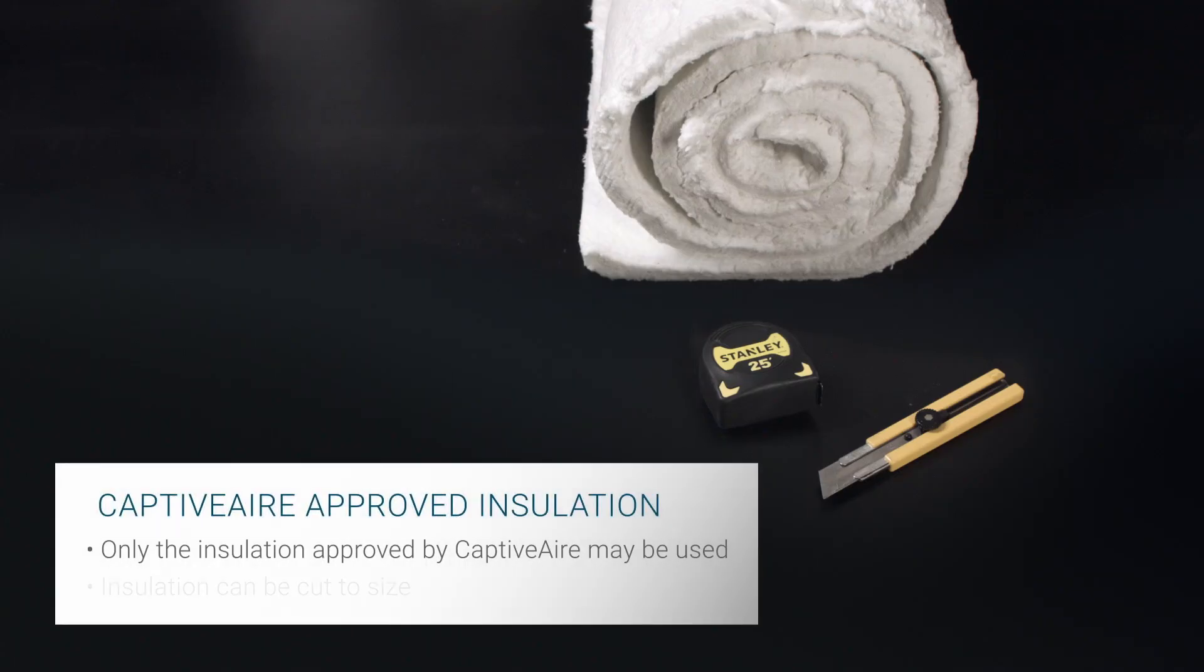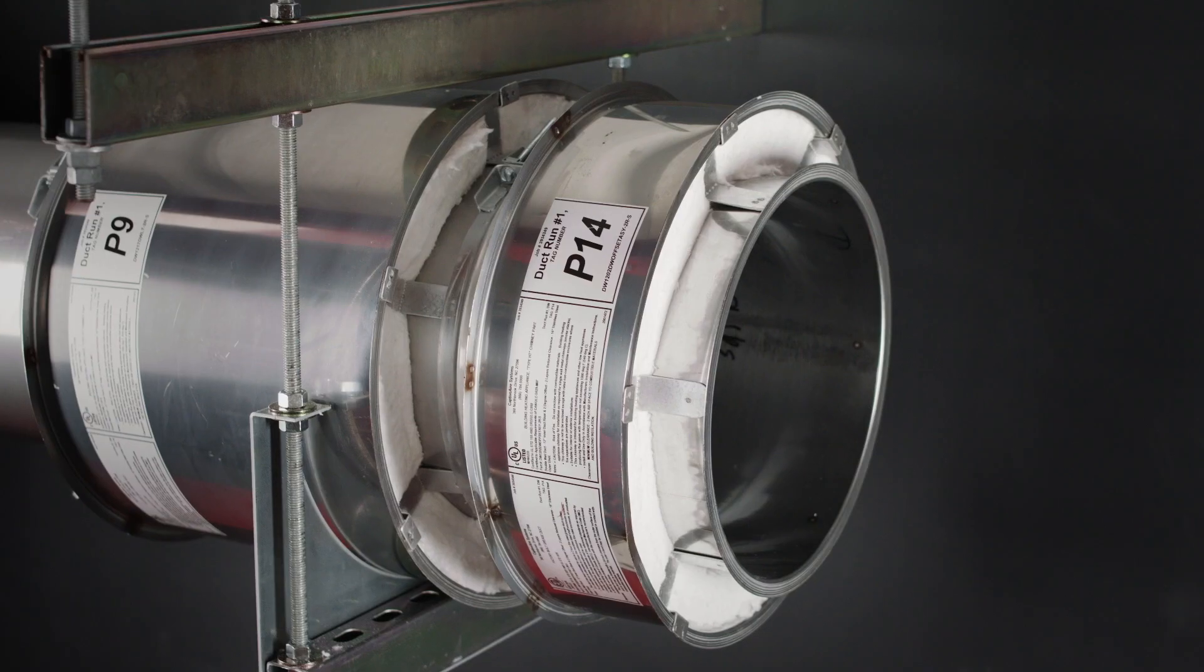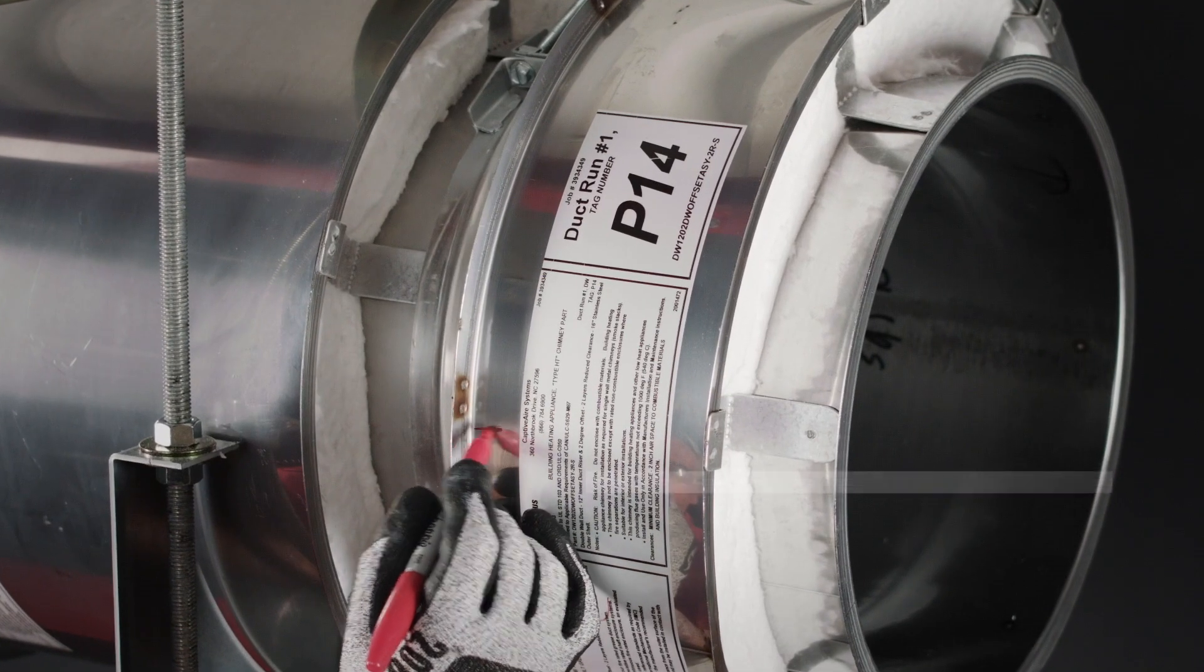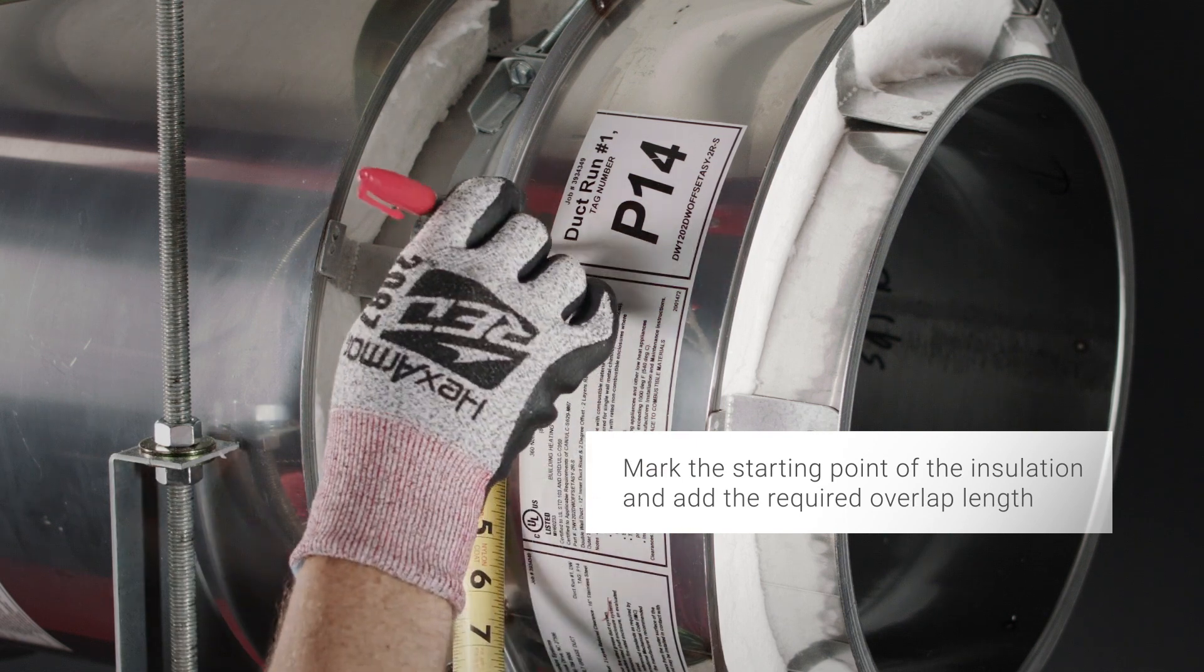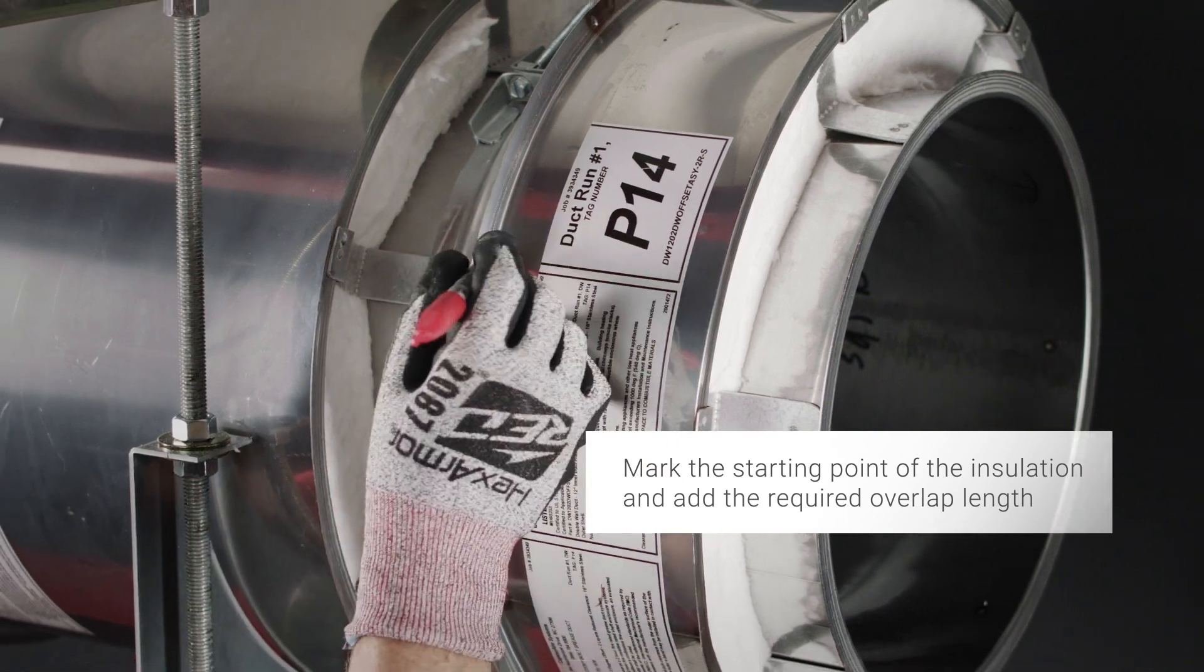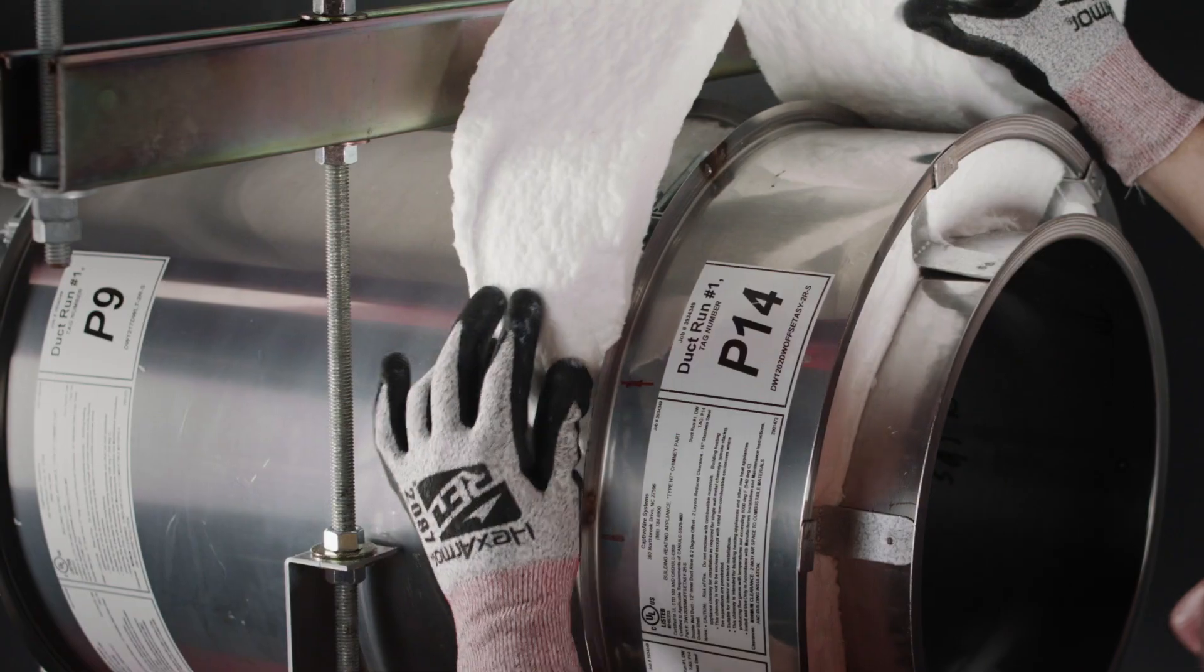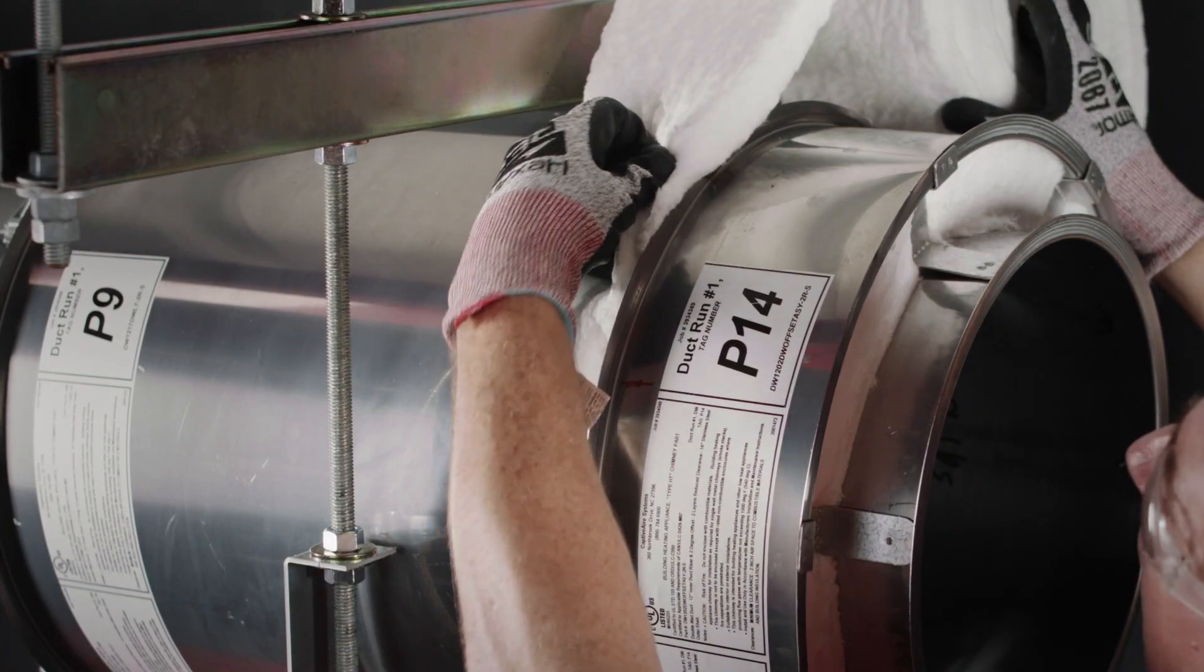You can now apply insulation around the duct. Insulation must be a minimum of 4.5 inches wide, and the same type and number of layers as the base duct. As a reference, mark the duct at the desired starting point of the insulation. Measure 3 inches from this mark, and add a second mark. These two marks will guide you in setting the correct insulation overlap of 3 inches.